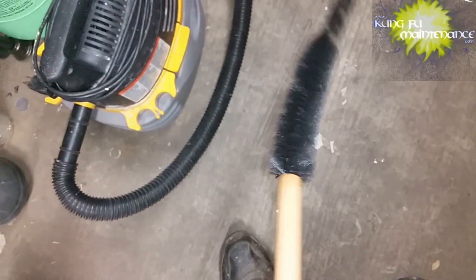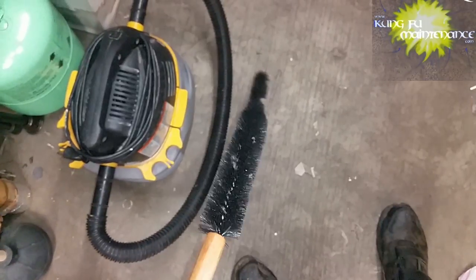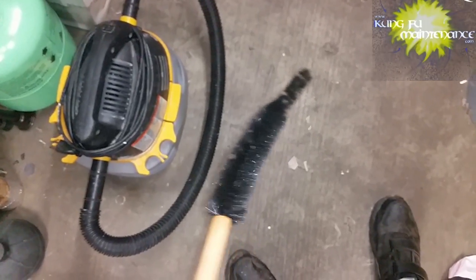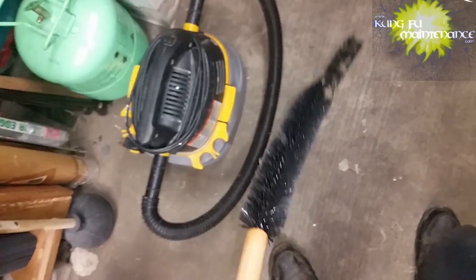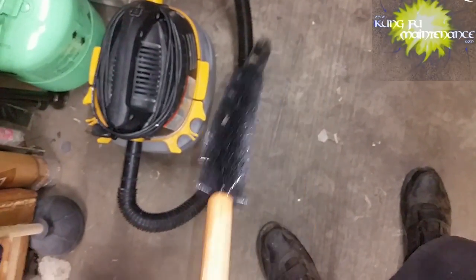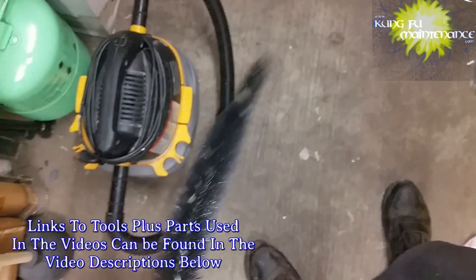That's not freezing ice cream. Sometimes it can just be a dirty coil. It doesn't take but a few 10 degrees difference. Sometimes if you have just a low temperature difference, it can be just from a dirty coil. And so it's kind of one of the first things to try. Also want to make sure that there's no ice blockage in the condensate drain, because that can also cause it not to be getting cold in the refrigerator.